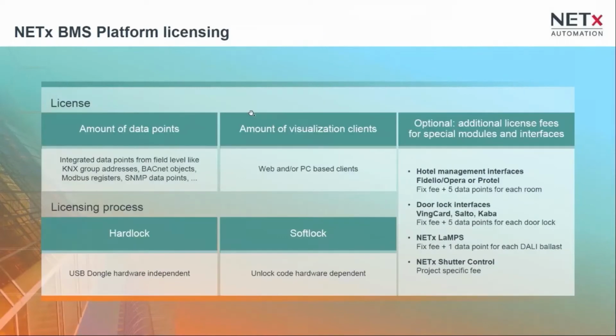Generally, we license according to the number of data points from the field and automation level only, the number of included visualization clients, which means simultaneously connected visualization clients, and the optionally available specific interfaces and modules like the hotel property interface, door lock system interface, DALI lighting system, or shutter control. And licensing can be provided, like you know from the ETS, in a hard lock USB dongle, or with a soft lock license, which is related to your operating system.